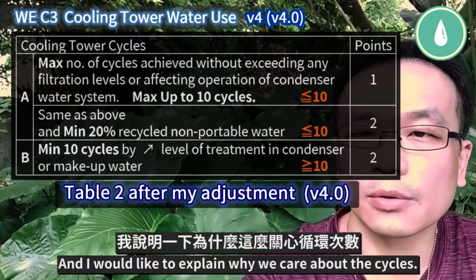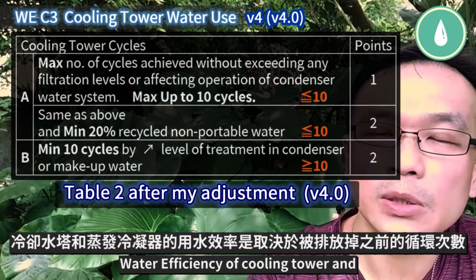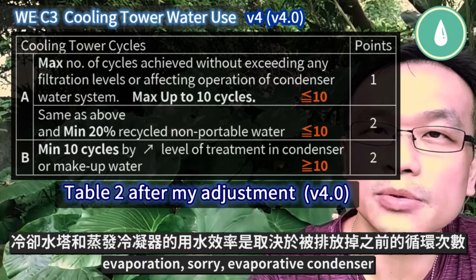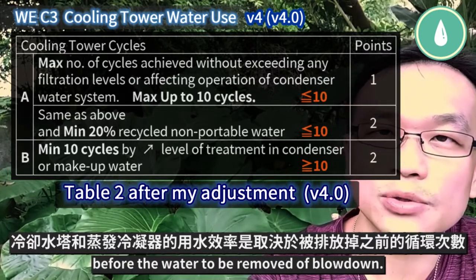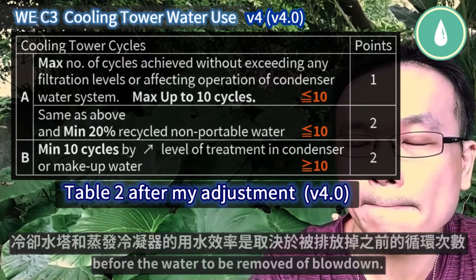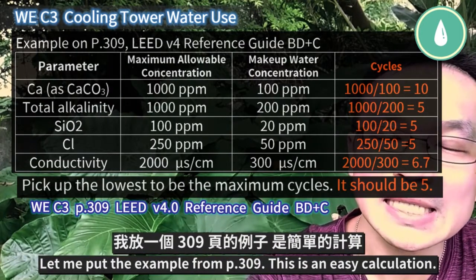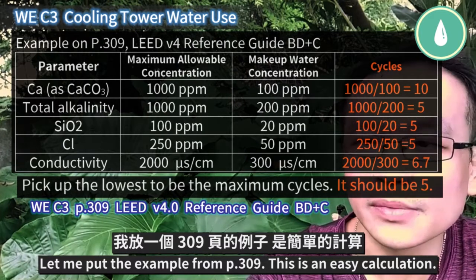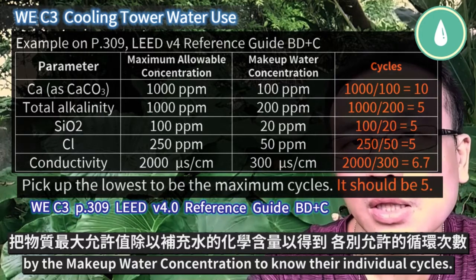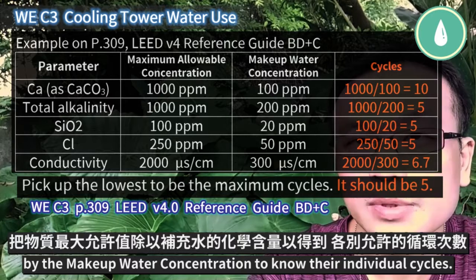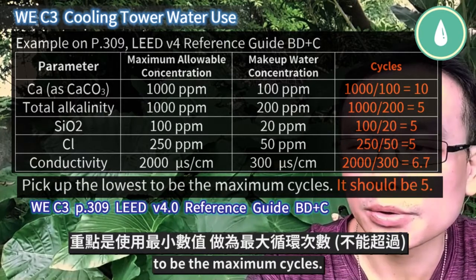I would like to explain why we care about cycles. Water efficiency of a cooling tower and evaporative condenser is measured in recirculation cycles before the water is removed by blow down. Let me put the example from page 309 — this is an easy calculation. You divide the maximum allowable concentration by the makeup water concentration to find individual cycles, then pick the lowest number as the maximum cycles.